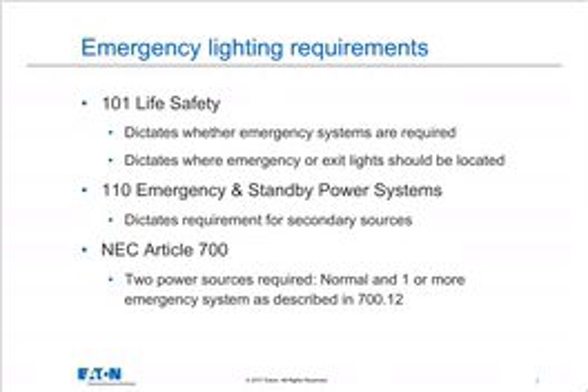Now, NFPA 110 concerns itself with emergency and standby power systems, like you might find in a hospital, for example. So that's both things like UPSs, but also things like generators and power systems that are necessary to keep things running and keep the commercial facility or building in some level of operation for an extended period of time. Now, in the National Electrical Code, Article 700 talks about the different types of power sources that are required, and we'll see a little bit more of that as we move along.